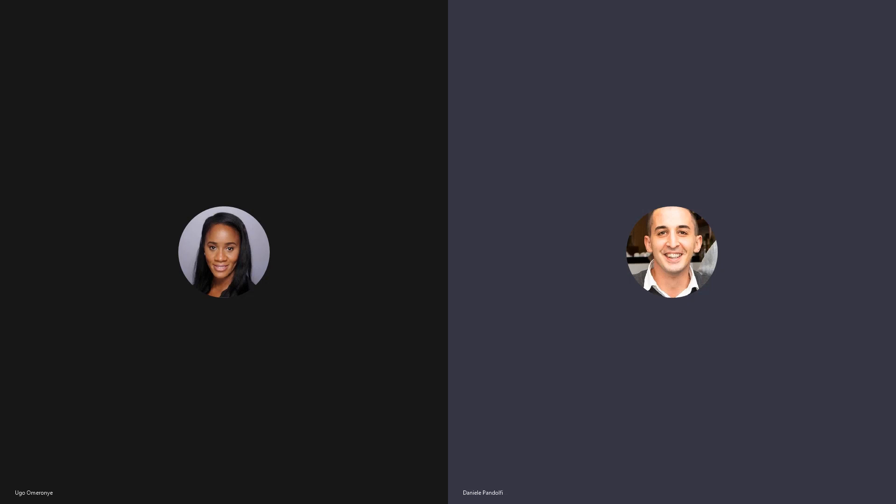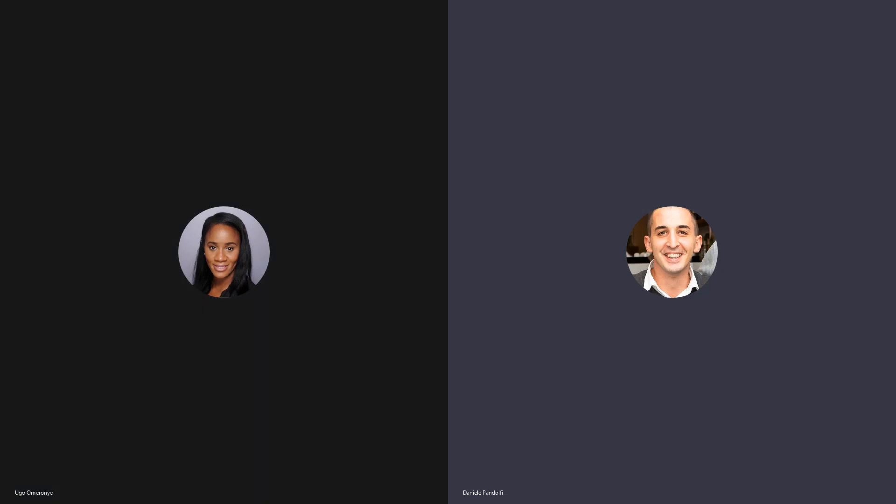On the other hand, when we go into the core of the cleanroom where your critical data are generated, where your product is filled up into your vials or whatever container you use, then it's better to use a dedicated system. In this case, the EMS to differentiate between the two, to let the EMS be in charge of handling your critical data and the BMS being in charge of controlling all the automation that are typically not critical for the release of the product. So short answer is both, each one for the specific application.